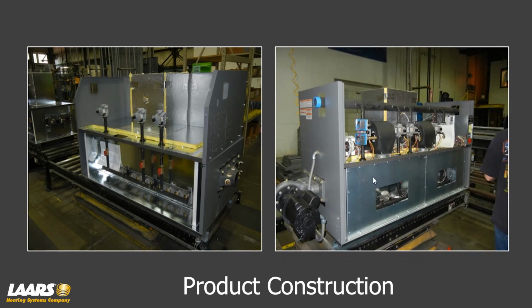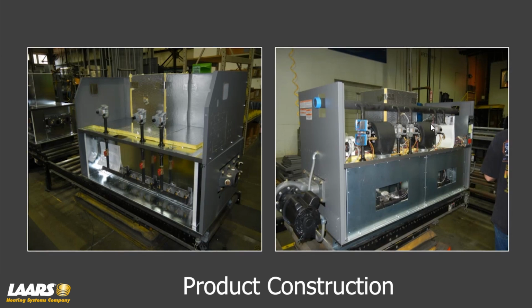The right-hand image here, I'm showing something greater than a 1,250,000 BTU boiler. How I know that is we have two blowers in this. Now, we have a common gas train that comes through the top of the boiler, and that could be piped either left or right-hand configuration. There'll be a cap on one side. It all depends on how you order it. If you order it right-hand, then your cap would be on the left-hand side. So that's a common gas train that comes out and feeds down to each gas valve. And we'll talk about measuring incoming gas pressure in this presentation.